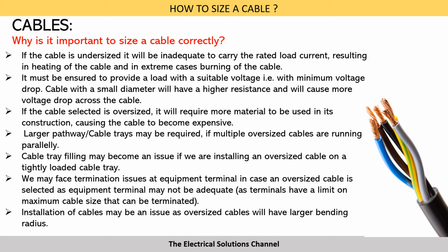If the cable is undersized, it will be inadequate to carry the rated load current, resulting in heating of the cable and in extreme cases, burning of the cable. Cable size should be such that the load is provided with a suitable voltage. That is, there is only a minimum voltage drop. A cable with a small diameter will have a higher resistance and will cause more voltage drop across the cable.